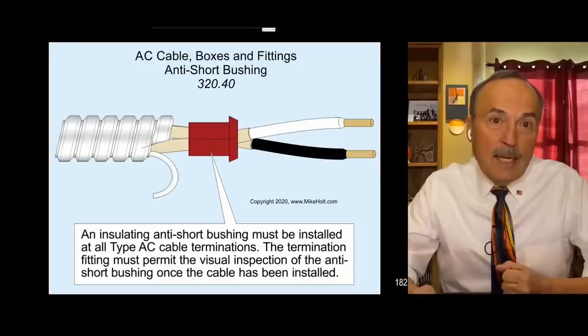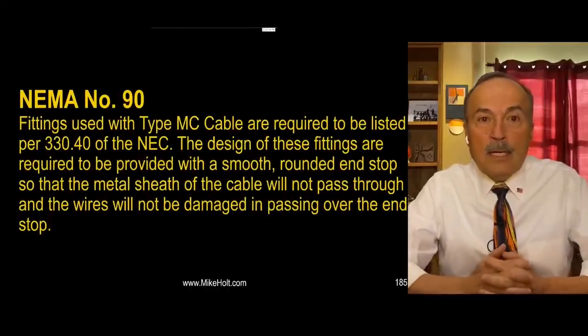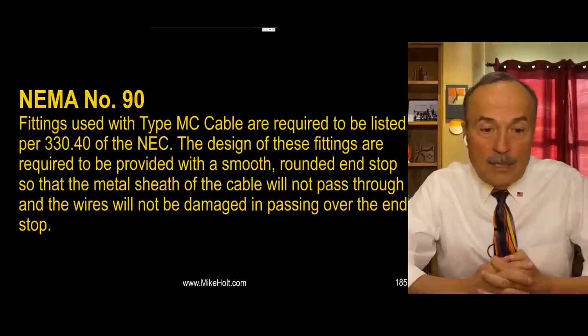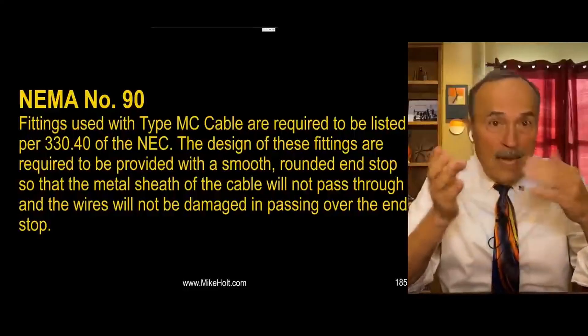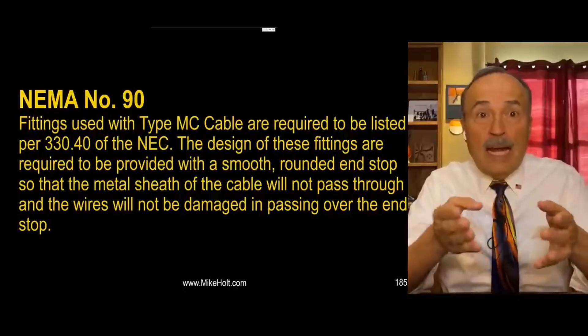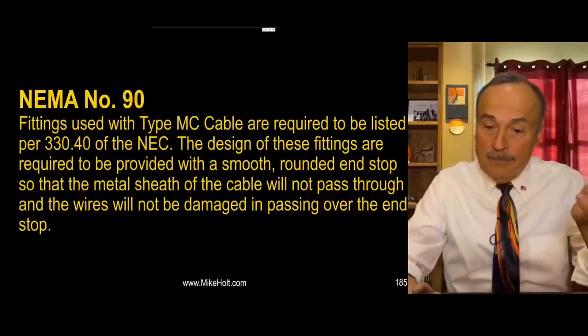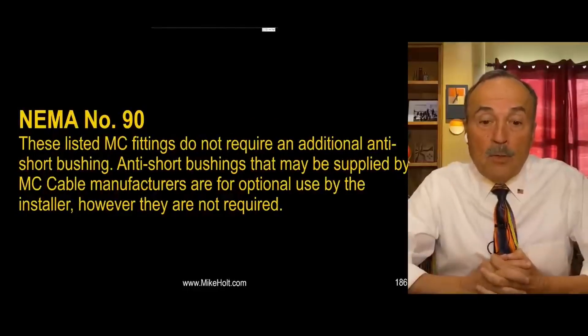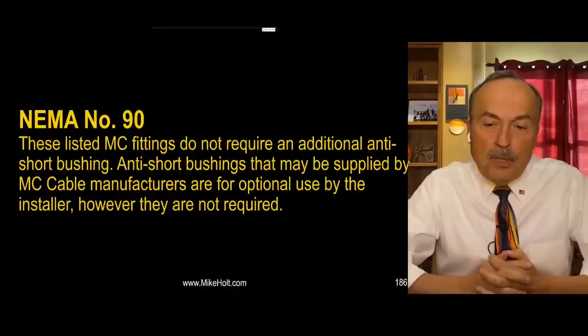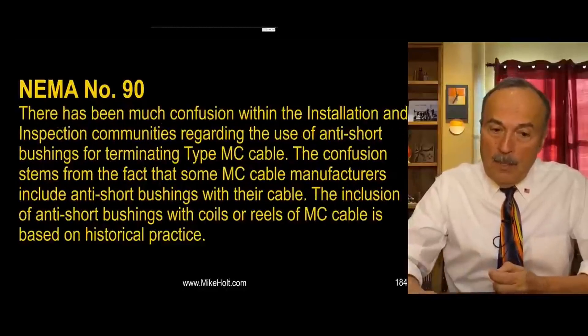Fittings used for type MC cable are required to be listed per 330.40 - similar to 320.40 but talking about fittings. The design of these fittings is required to provide a smooth rounded end stop so the metal sheath won't pass through and the wires won't be damaged. That's a special fitting - that's why you don't need anti-short bushings. These listed MC fittings do not require an additional anti-short bushing. Bushings that may be supplied with MC cable are an option, not a requirement.